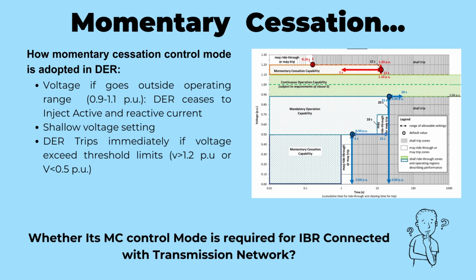Let's explore the use of momentary cessation control mode in distributed energy resources, or DER. The IEEE 1547 standard provides voltage requirements for DER, shown in a voltage curve. If the voltage goes outside the range of 0.9 per unit to 1.1 per unit, the DER can either momentarily stop supplying active and reactive current or have the ability to ride through voltage fluctuations. Beyond this range, the DER has the option to either ride through the voltage deviation or activate a trip function. The decision on whether to use ride-through or trip function is typically made by distribution system companies and DER owners. However, many DER systems have chosen the trip function and have not implemented ride-through capability, as it was not mandatory.